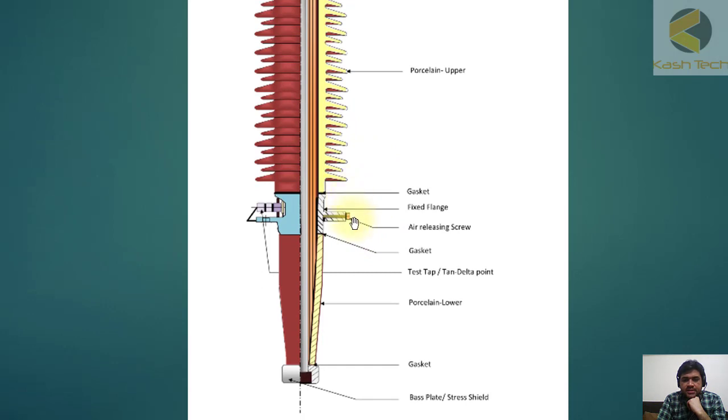Again there is a gasket, then there is a flange. Here is an air releasing screw. When a transformer is energized for the first time, air is trapped under the bushing, so bleeding is done at this point. Then we have a gasket. This point you can see is the test tap tan delta point for doing the tan delta measurement.